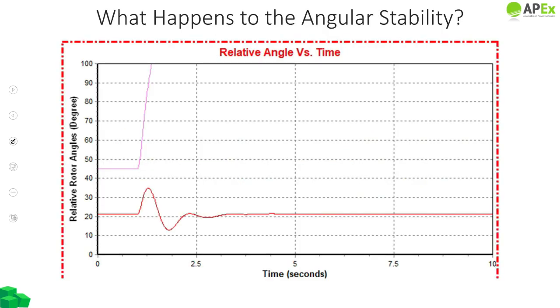Here is our result. Indeed, limiting the capacity on the transmission line has helped to keep our system stable. In the red line, we have our relative angles after reduction of load, while in the pink line we have the results that were previously shown. When the fault occurred, our rotor angles continued increasing and became unstable in our first example. When we reduced the transmission capacity, yes, there was a disturbance here, but this disturbance got cleared and the system became stable.